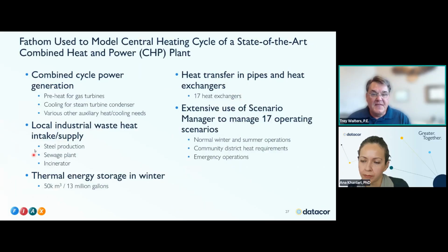Some of the things they did in here, this was a very wide-ranging case: the combined cycle generation, different operations in there for pre-heat for gas turbines, cooling, for steam turbine condenser, et cetera. They were integrated with the local industrial waste heat coming from steel production, a sewage plant, an incinerator. They stored up to 50,000 cubic meters of energy, and 13 million gallons that they could use in winter. They had like 17 heat exchangers, and again, they had like 17 operating scenarios. So if you want to read about that, again, it's on our website, and I think also in the handouts.